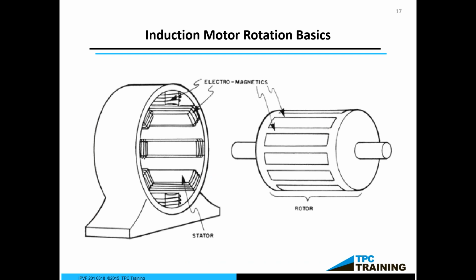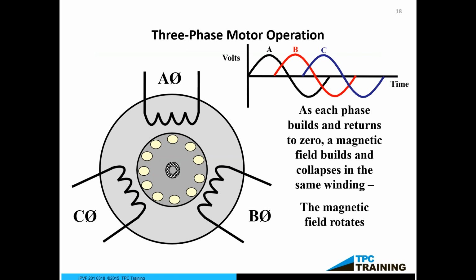Understanding drives, well, drives, you have motors, and so motor theory is very, very important. So whether it's single phase or 3-phase motors, it's just very, very important to understand motors and how to test motors. Most of our stuff is 3-phase motors, but it doesn't have to be 3-phase motors. It could be a single-phase motor also. ABC, 1, 2, 3, black, white, red, whatever your color, Y or delta, and each of those particular configurations are depending on the application, whether it's Y or delta, or whichever your voltage happens to be.